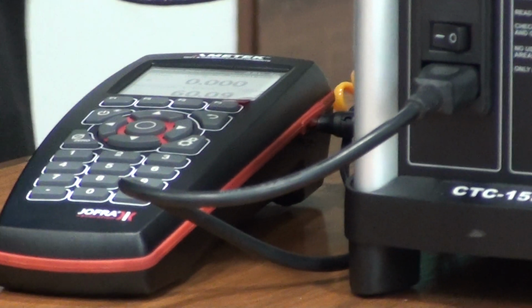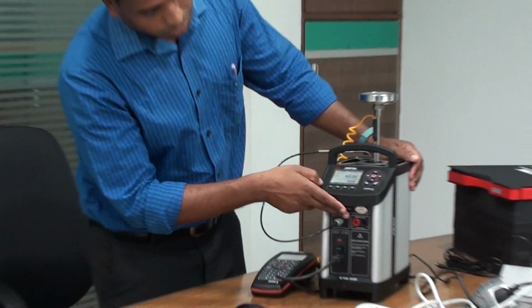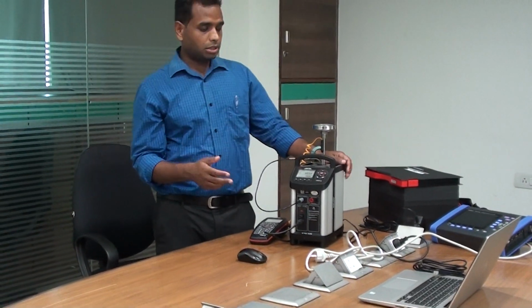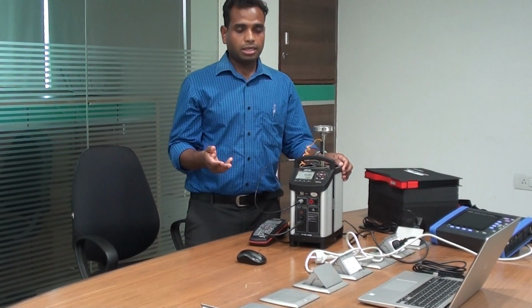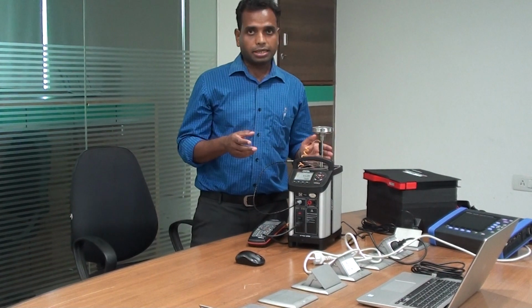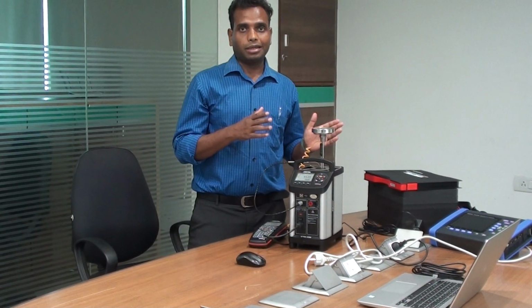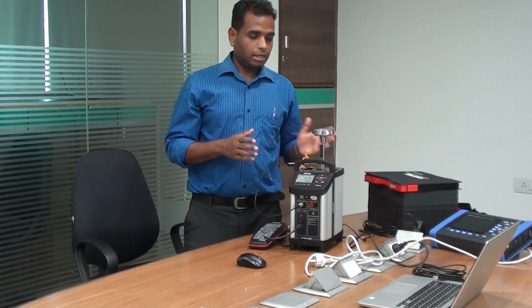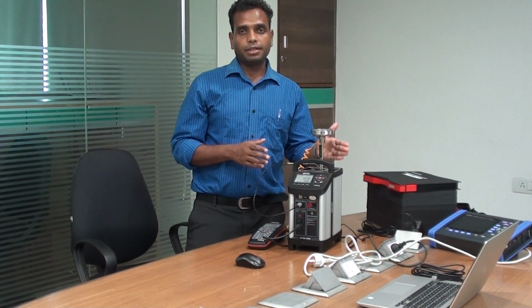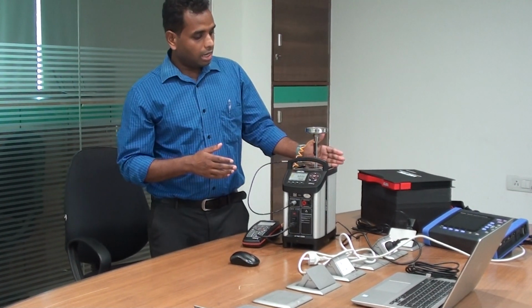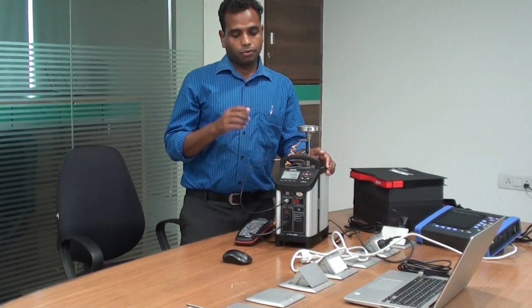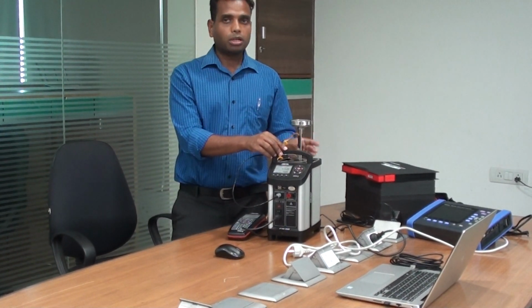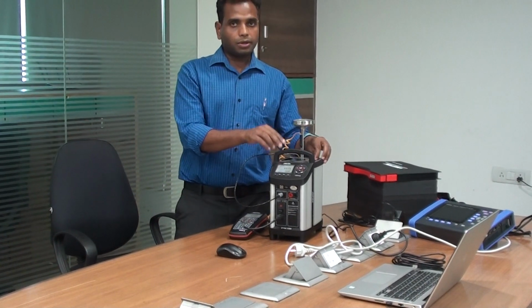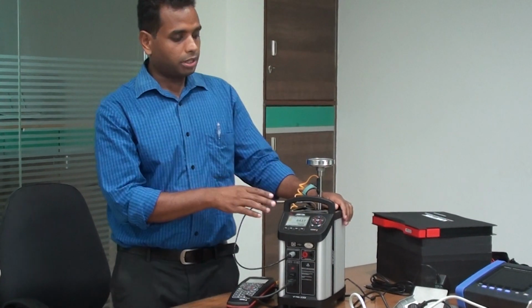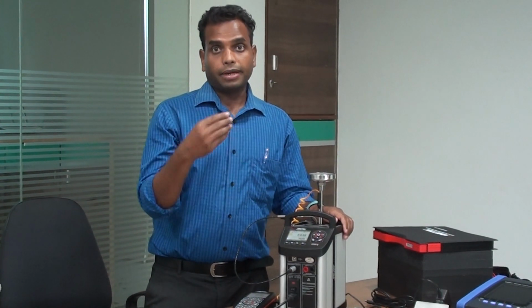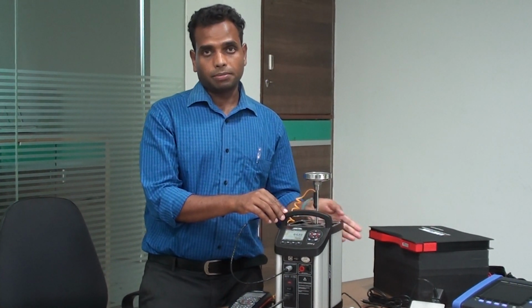So we'll take one more feature until that gets stable. There is a switch test option. Switch test is for temperature switches, which are generally used in the process industry, and a temperature switch has set criteria like lower limit, upper limit, band time, and temperature rise time. If the lower limit is set for 50 degree and the upper limit is set for 60 degree, and the temperature increase is 1 degree per step, there should not be 2 steps. If it is moving 1 step at a time, one by one, it is okay.